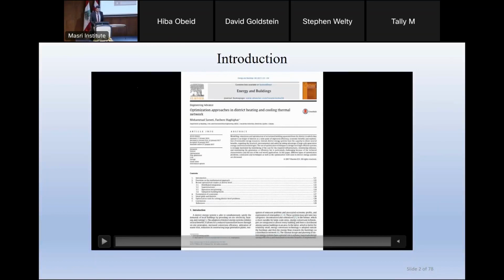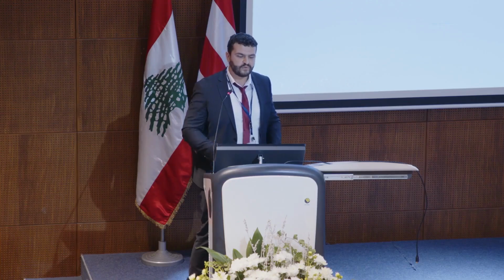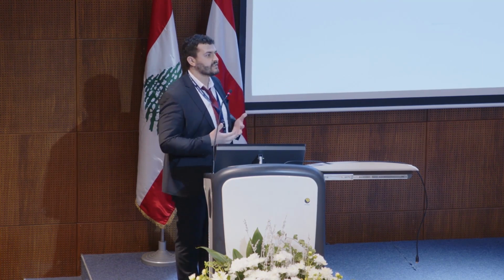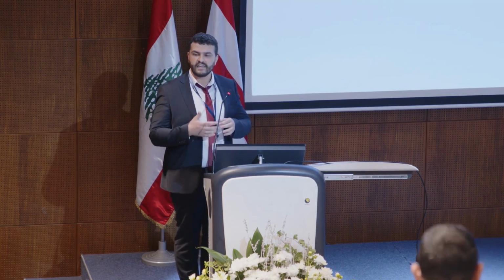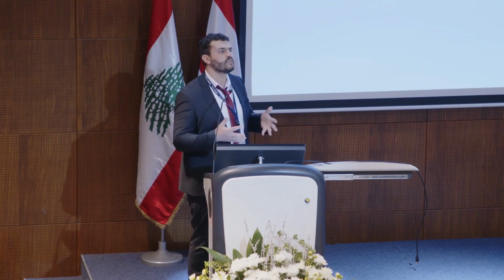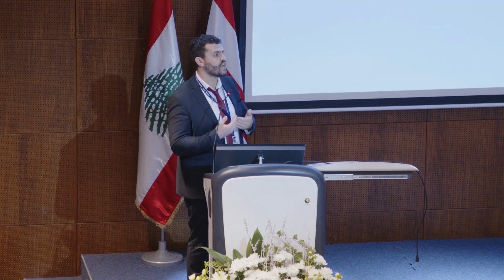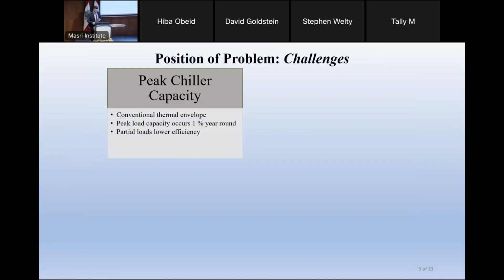But what are the challenges facing these researchers? First is the peak chiller capacities. Most consultants, when designing buildings, choose the chiller capacity based on the peak load, which only occurs for about 1% of the year. This increases capital cost and also operational cost, because chillers work most of the time at partial loads, which have lower efficiency.